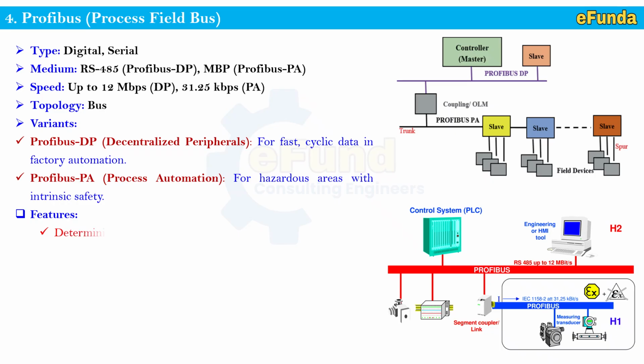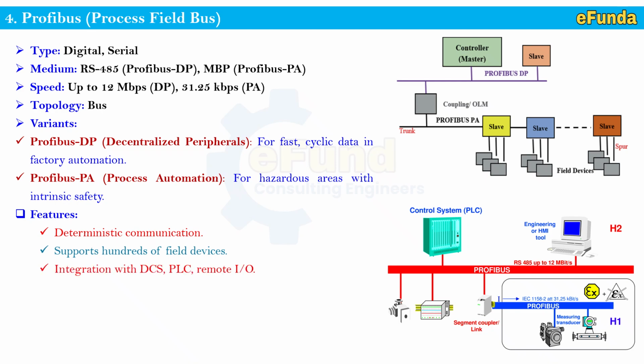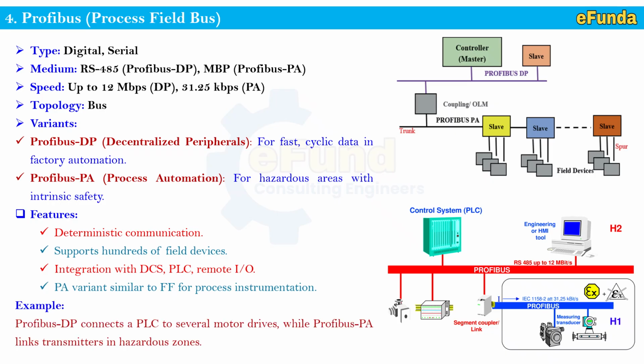First, deterministic communication. Second, supports hundreds of field devices. Third, integration with a DCS, PLC or a remote IO system. Fourth, PA variant similar to Foundation Fieldbus for process instrumentation. Example: Profibus DP connects a PLC to several motor drives, while Profibus PA links transmitters in a hazardous zone. This is how the Profibus protocol is being handled for interfacing field devices with the control system.